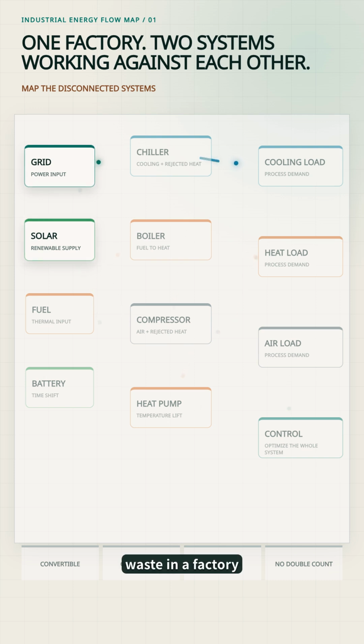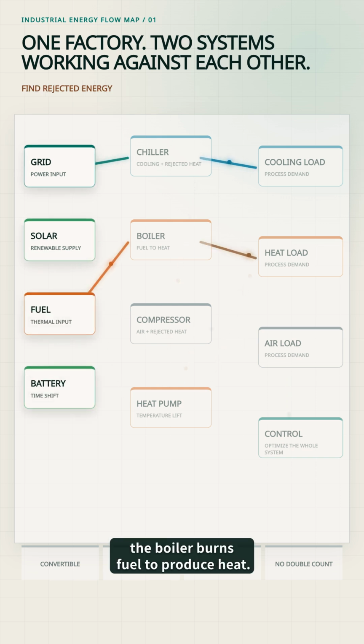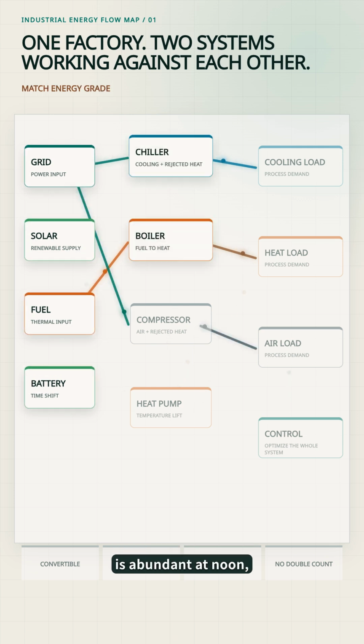The biggest energy waste in a factory is often not an inefficient machine. It is two systems doing opposite things at the same time. The chiller plant rejects heat while the boiler burns fuel to produce heat. Air compressors discharge high-temperature heat while a cleaning line still uses steam. Solar power is abundant at noon, while chillers and heat pumps run during the evening peak. Those are the problems industrial energy integration is meant to solve.